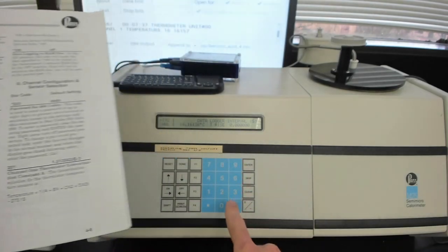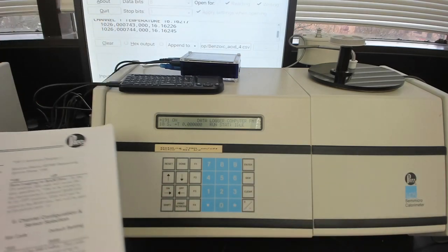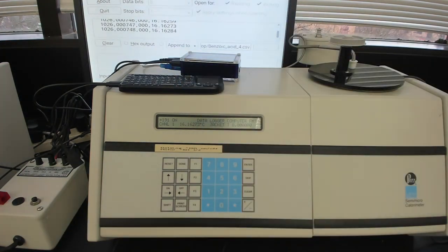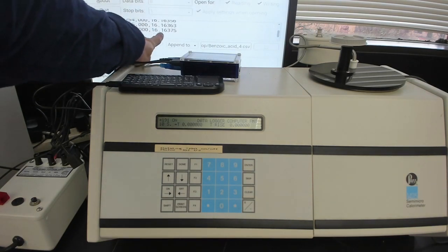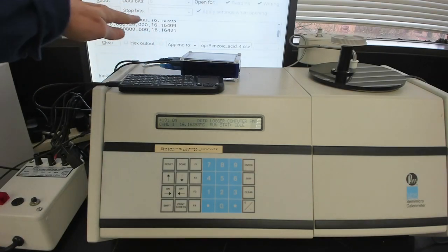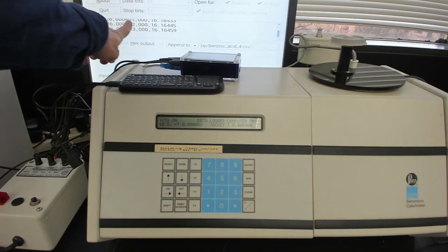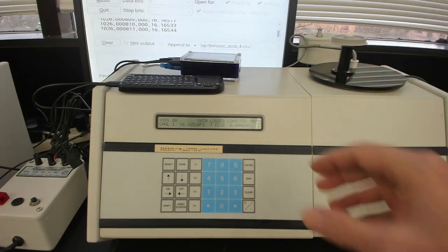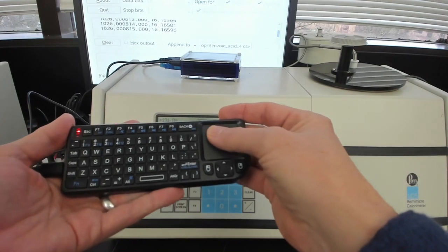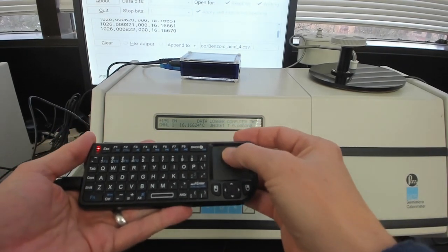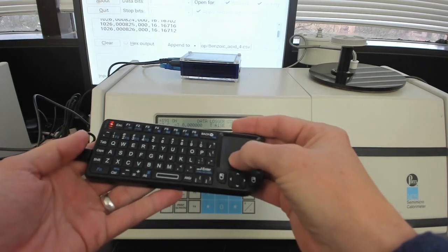Yeah, there we go. And then to get rid of all that text, we put in data logger computer format, star 191, enter, and we do on. Oh yeah, you don't have to hit enter when you just do on and off. And so there's our computer compatible data. We don't really care about these first three columns. We're just after the temperature column. I haven't found a way to clean it up any better than that. But this is really seconds. It's a data point in seconds. So that's the data. Now, in order to capture it, we need to come down here and let's see. There's like enter or something to get it. Yeah, there we go.